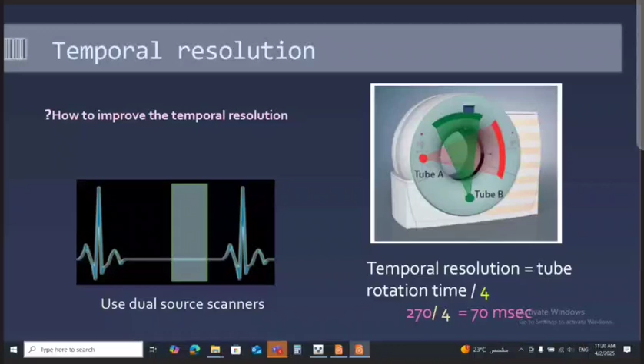You can imagine this tube, the red tube, will move to this side, and the green one will take the side of the red one, so each of them moves 1/4 of the cycle, resulting in irradiation of half the cycle. And so the time needed for acquisition is the tube rotation time divided by 4, not by 2. This greatly improves the temporal resolution, and so in scanners with dual source, we can scan heart rates higher than 70 beats per minute.